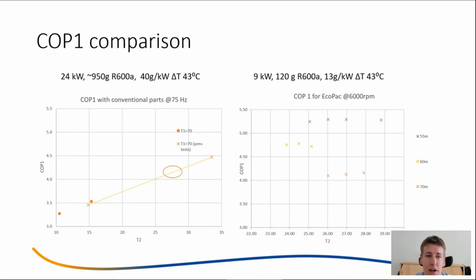And then you can say this was kind of dull. Didn't we make something new, something better? But if we look at the charge filling, for the standard component we used around 40 grams per kilowatt when we had a temperature difference of 43 degrees. If we look at the new system, we only use 13 grams per kilowatt at the same temperature difference. So I think here we have really proven that it is possible to build systems that use a lot less refrigerant and still match the same performance, which is actually what we were hoping for.